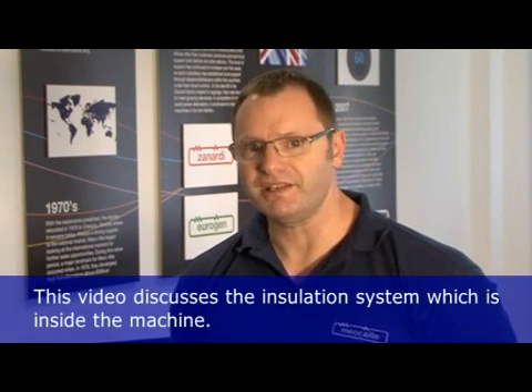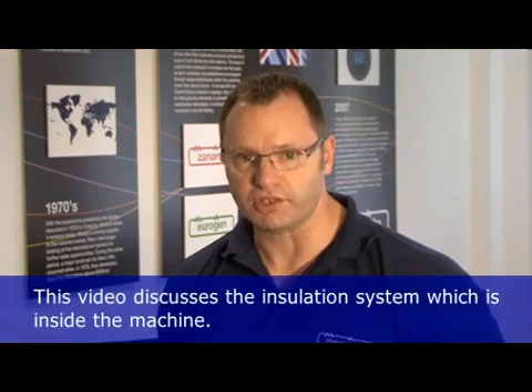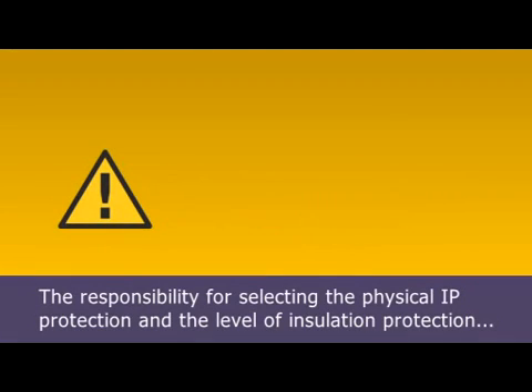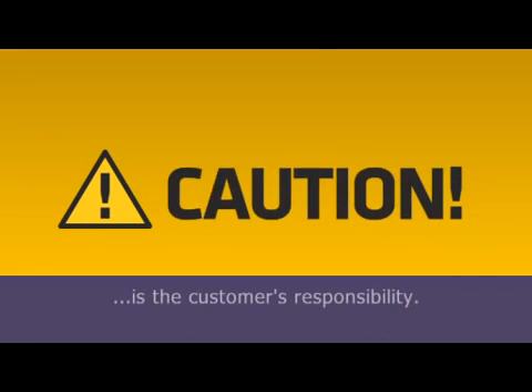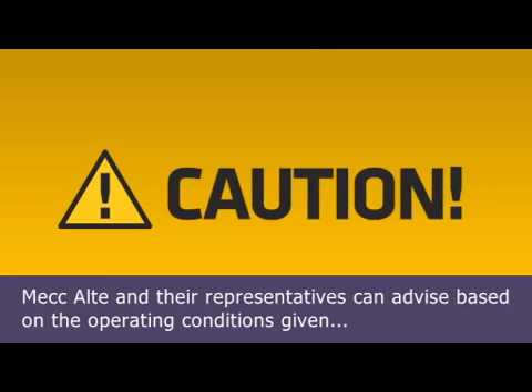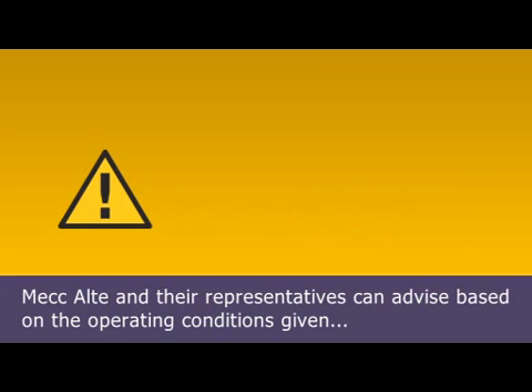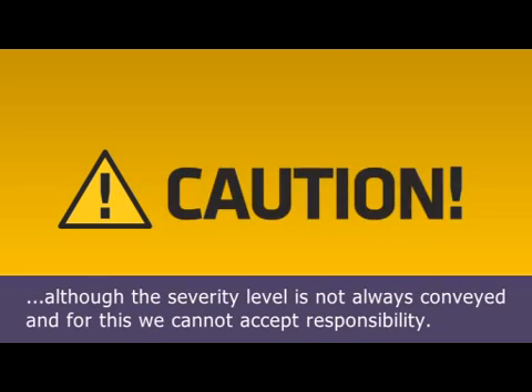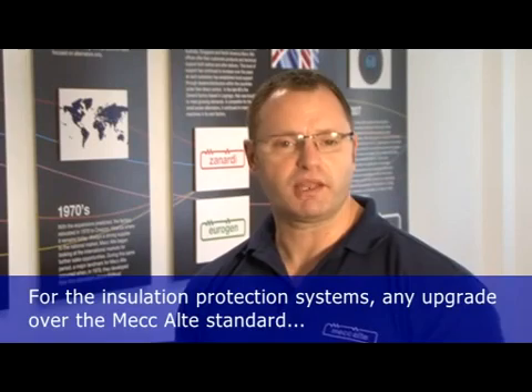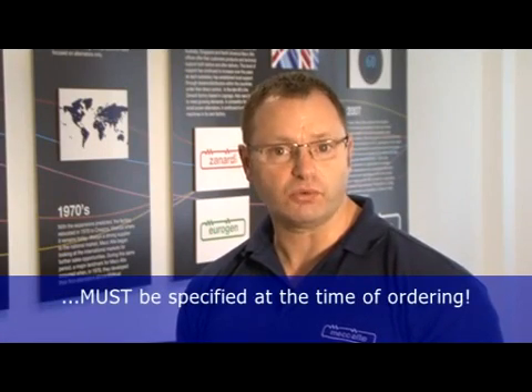This video discusses the insulation system which is inside the machine. The responsibility for selecting the physical IP protection and the level of insulation protection is the customer's responsibility. Mecc Alte and their representatives can advise based on the operating conditions given, although the severity level is not always conveyed, and for this we cannot accept responsibility. For the insulation protection systems Mecc Alte offer, any upgrades must be specified at the time of ordering.